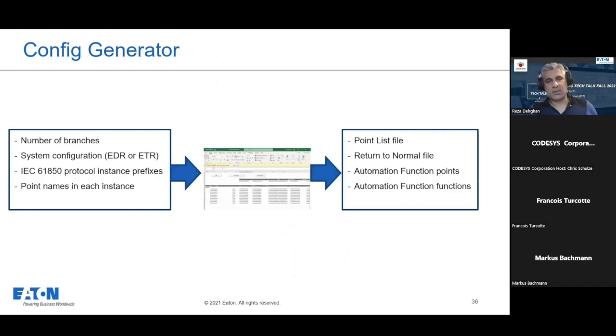Yeah, this is just the idea of that spreadsheet with macro. On the left side, this is the information that I feed to the Excel sheet. On the right side are the things that I get from that macro. So on the left side, I just say what's the number of the branches. System configuration is another thing that I have to specify, whether it's using ETR-only relays or EDR. As I said, EDR is not necessary for now, but we made it so it's future proof. And then the IEC 61850 protocol instance prefixes. These are some settings in SMP Gateway. And then finally, the point names in each instance.